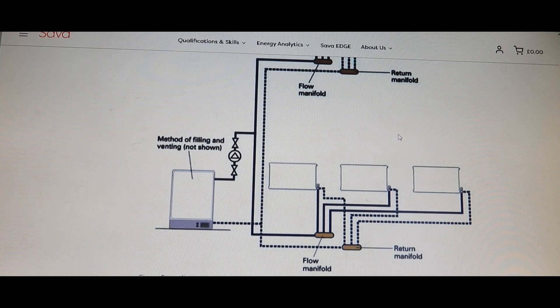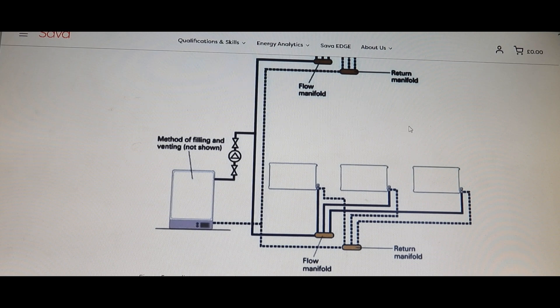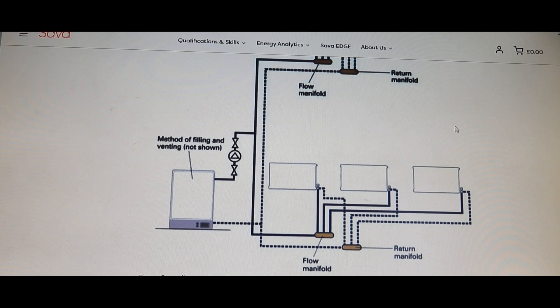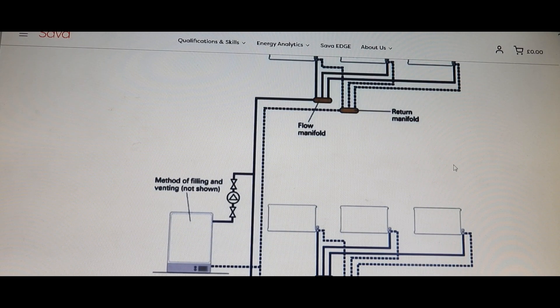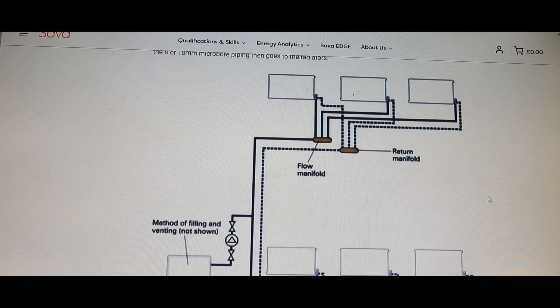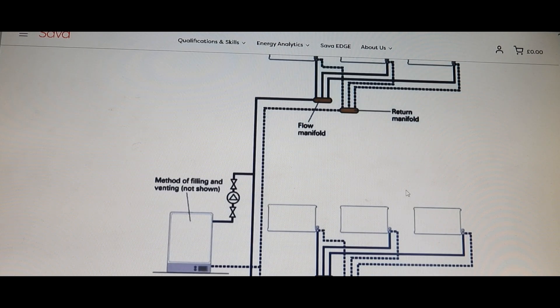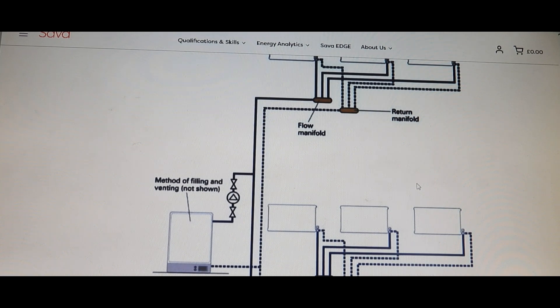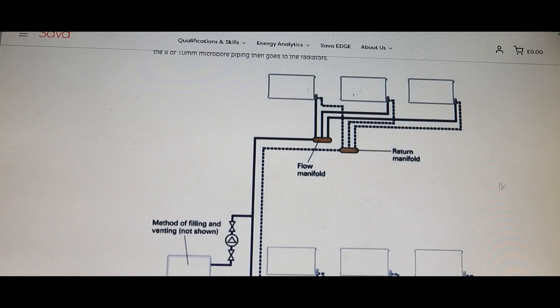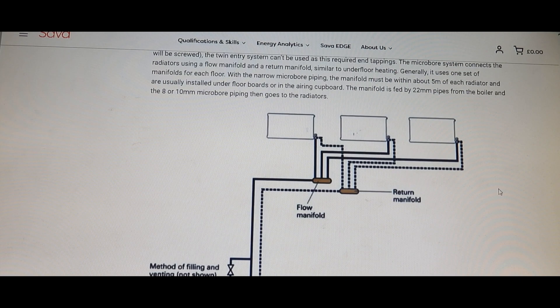Now talking of blocking up, the other main thing that's got to be done all the time with these radiators with a microbore system is to make sure you've got plenty of inhibitor in there so that everything is running clear. Make sure that is checked regularly with an inhibitor tester to make sure that you've got the right and correct levels functioning in there to keep these systems clear, because the main thing that goes wrong with these systems is sludge in that microbore pipe.